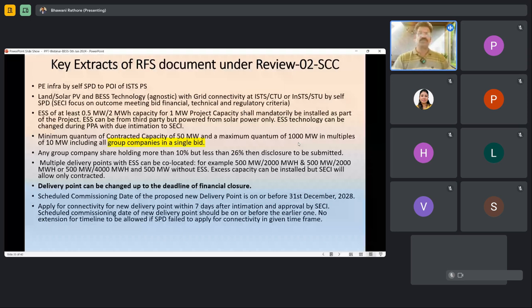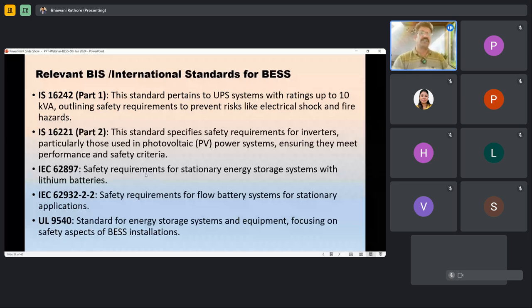IEC 62897 is the safety requirement for stationary energy storage systems with lithium batteries. IEC 62932 is the safety requirement for flow battery systems for stationary applications. UL 9540 is the standard for energy storage systems and equipment. Right now India is following these international standards only for BESS because we don't have our own standards for these parts; we only have standards for UPS and inverter.